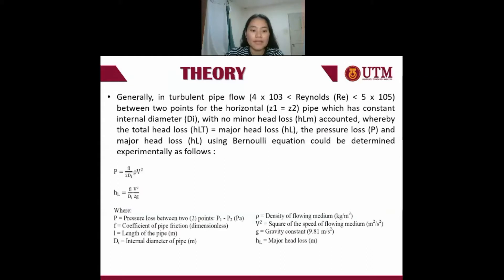For the major head loss, it is equal to the coefficient of friction multiplied by length, then multiplied by the square of the flow speed, divided by the internal diameter multiplied by 2 times the gravitational constant, giving the major head loss.